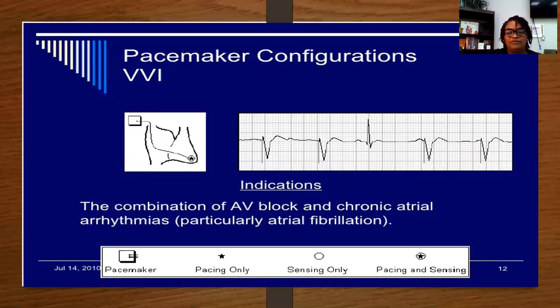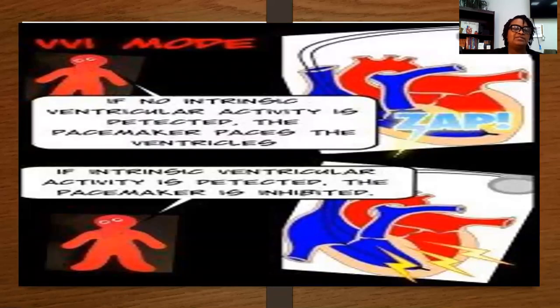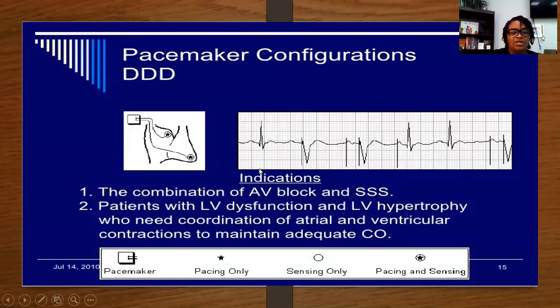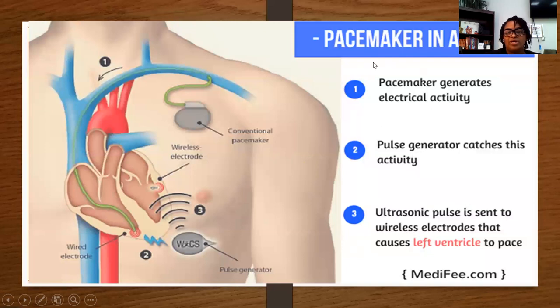Here's an illustration of your VVI. When you have VVI mode, if no intrinsic ventricular activity is detected, the pacemaker paces the ventricles. So here that pacemaker is going to fire. But if intrinsic ventricular activity is detected, then the pacemaker will be inhibited. So it'll just sit still and wait. Okay, here's an illustration of your triple D pacemaker. And then let's see the pacemaker in action.